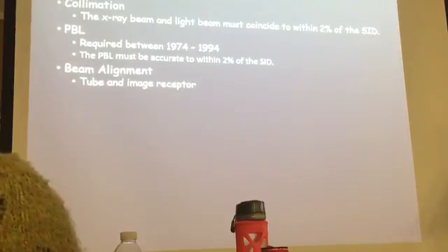And it begins to shoot X-rays in different directions. Or you as an X-ray tech, if you are too rough with the X-ray tube and bang the tube against a wall or against something, that can also shift the X-ray tube. And then your beam is not perpendicular, and that creates problems because where you think the central ray is, it's not. You see the light, you see the central ray, but then the actual beam is going to be off. So that's another test that you do along with the beam alignment.